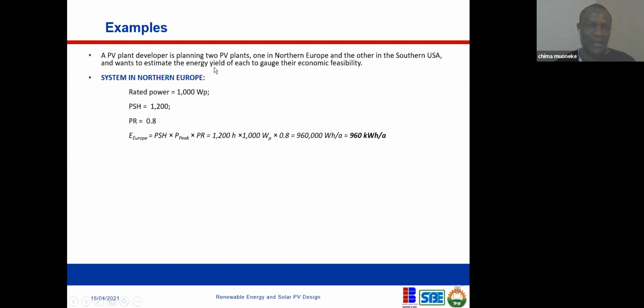So this developer wants to determine the energy yield he will get from this system. The energy yield in Europe becomes the peak sun hour, 1,200 hours, times the rated peak performance of the solar module, 1,000 watts, times the performance ratio of 0.8. When we do that computation, we get 960 kilowatt hour per annum - the amount of energy you can get in a whole year from that system.